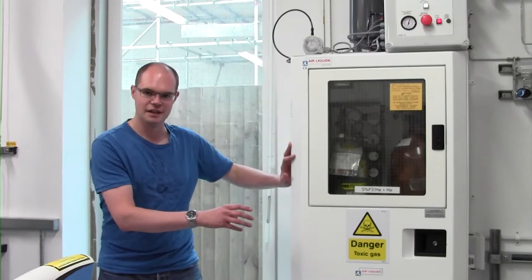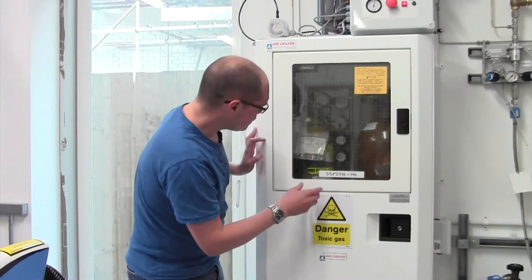We have it 5% concentration and a 95% balance of helium. So, reasonably low concentration in the helium. We keep it safe inside this cabinet. We normally have an extraction system on, so if we were to have a leak, it gets sucked out of the room.